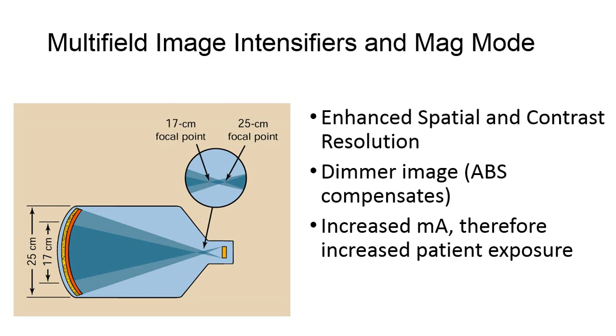This also causes the image to be much dimmer. When there is less input light, the minification gain is reduced. We'll talk about automatic brightness control soon, which should compensate for this loss of brightness, which causes a lower signal-to-noise ratio. Unfortunately, mag mode requires increased mA, so skin dose does increase for the patient. The radiologist must consider all of these factors when opting to operate the fluoroscope in magnification mode.